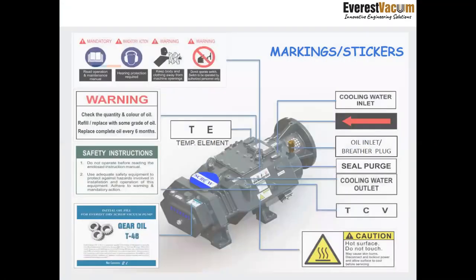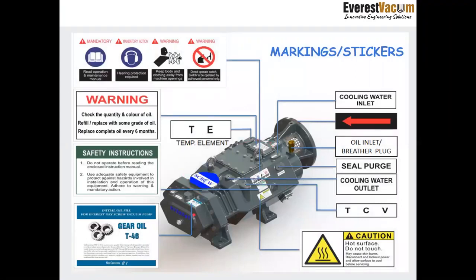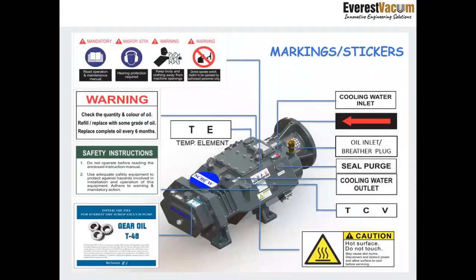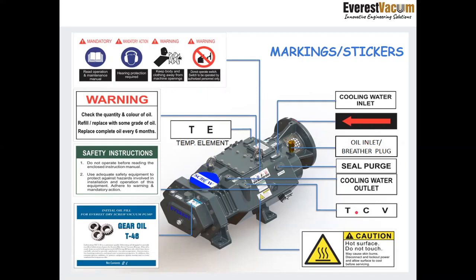Now coming to the operation and maintenance part, there are certain markings and stickers available on the pump, and I want to brief you on them. As you can see, it is a dry screw vacuum pump. There are stickers engraved on it, like for the cooling water inlet, as it has a cooling water jacket to dissipate the heat. From one end towards the discharge, there is a cooling water inlet, and towards the suction, the cooling water comes out. It is oil lubricated on both sides, so there are oil filling ports, and the oil grade to be filled is also mentioned. Then there are cautionary signs for hot surfaces. Then for our CX series, the anti-corrosive series, there is a temperature control valve.